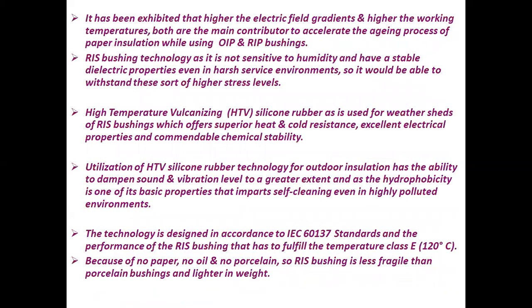It has been shown that higher electric field gradients and higher working temperatures are both main contributors that accelerate the aging process of paper insulation in oil impregnated paper and resin impregnated paper bushings. RIS bushing technology, as it is not sensitive to humidity and has stable dielectric properties even in harsh service environments, is able to withstand these higher stress levels.